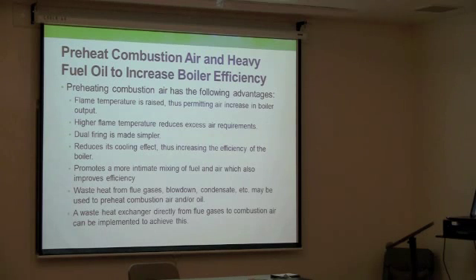If I have a boiler, just like the water normally comes here, steam is leaving the boiler, right? So the difference between the energy level of water, which is cold, and steam, which is hot, is the amount of energy that I have to burn here, right? It's different. So if I have warmer water, I'm going to have less energy to burn here. Very simple, right? So let's get this water, before it comes to the boiler, which is coming from the tap water, I take the tap water, I circulate it around here, which is hot, right? This is the flue gas. And then I bring it here.